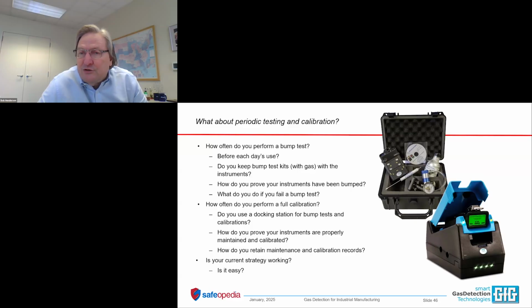We love packaging calibration kits or bump check kits or docking stations together with the instruments to make the obligation of testing and calibrating your instruments easy. You don't need a super expensive docking station. Well, ours is not super expensive, but you can get by with a very inexpensive small cylinder of gas and be fully conforming with OSHA and NFPA regulations and recommendations to perform a bump check before each day's use. But if you're following the OSHA best practice, if you're following NFPA guidelines, you really should consider packaging your instrument up with a kit that allows you to actually test according to requirements.